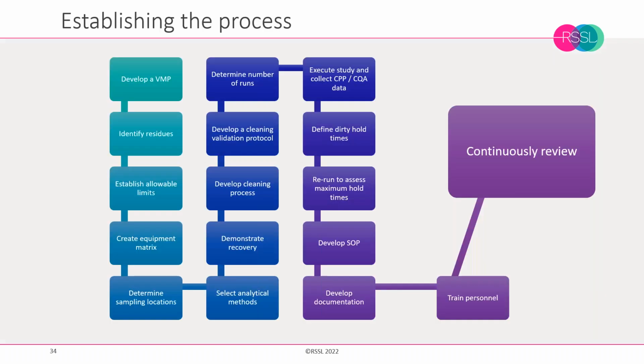For non-steriles, there's a very good paper, now getting close to 25 years old, from Doherty, and that gives some very good formulae for assessing the permitted microbial levels by working backwards from the finished product through the process, and it allows an expression of colony forming units per square centimetre. So the various factors I've mentioned all need to be put together, and this allows us to establish the cleaning validation process. I've tried to summarise that in a flow diagram of the various steps that need to be considered, which I won't go through now for the sake of time, but it's something you can have a look at, and hopefully that will present a good checklist for when you're putting together the cleaning validation and the associated SOPs.